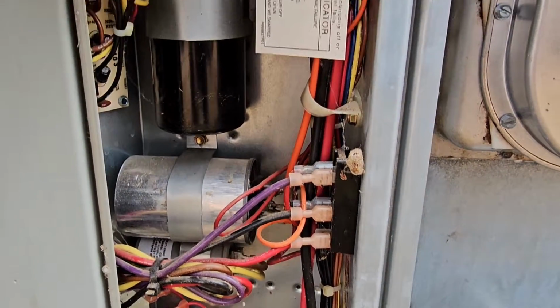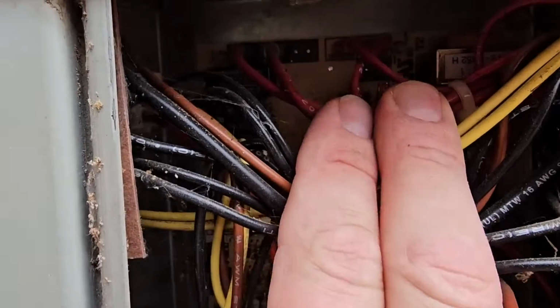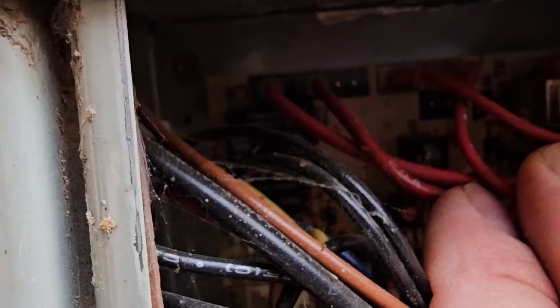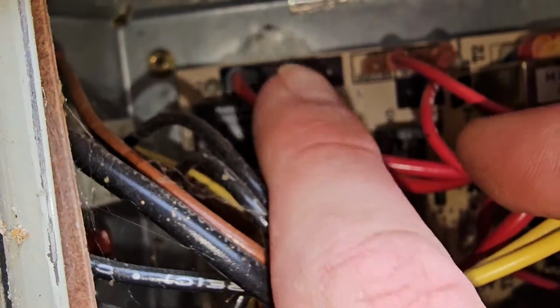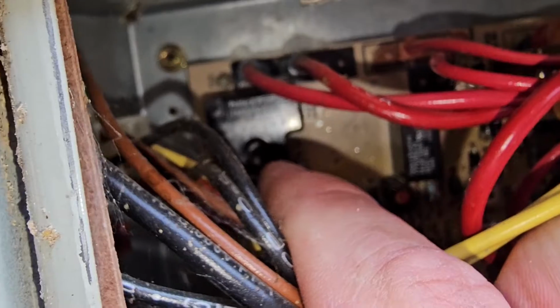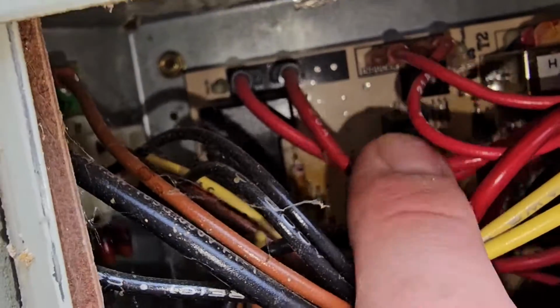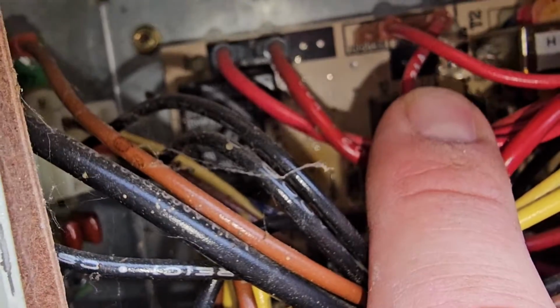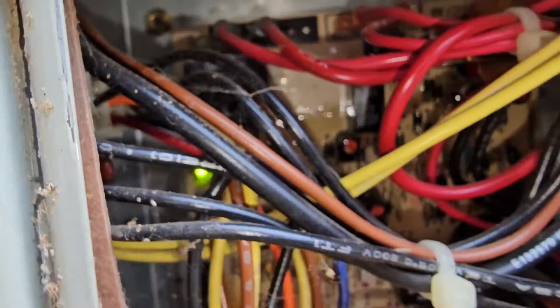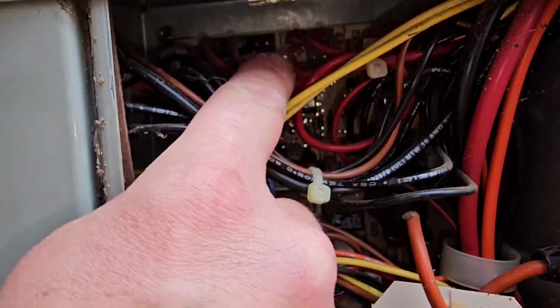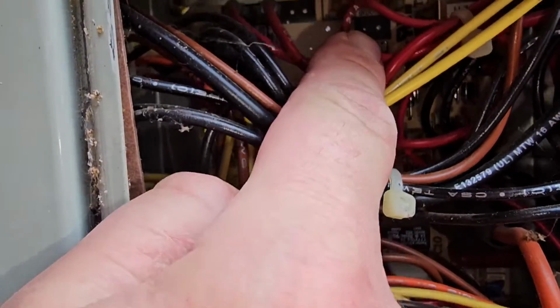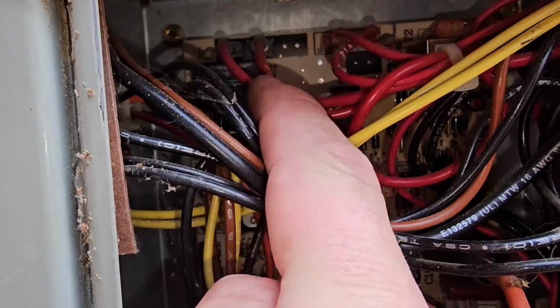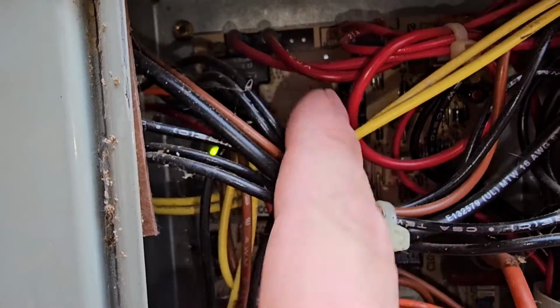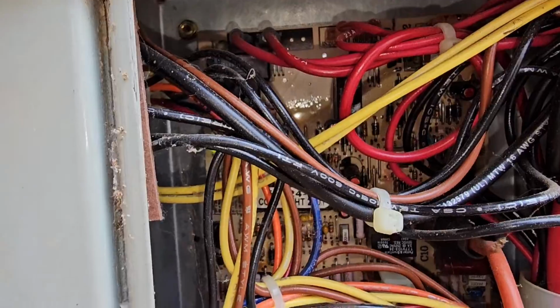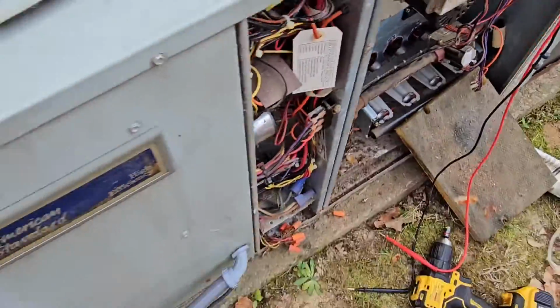And up here, if you can see, we've got a relay, right? We got a relay on the left that controls our indoor fan coming on, and a relay on the right that controls our inducer motor coming on. So if your inducer motor's not running, you may have a relay on the board that's not closing. If your indoor motor's not coming on, you may have a relay on the board that's not closing. I'll show you the schematic.